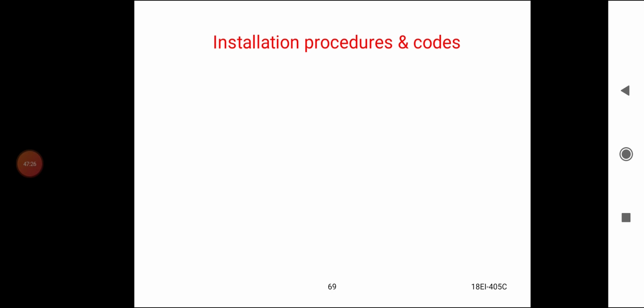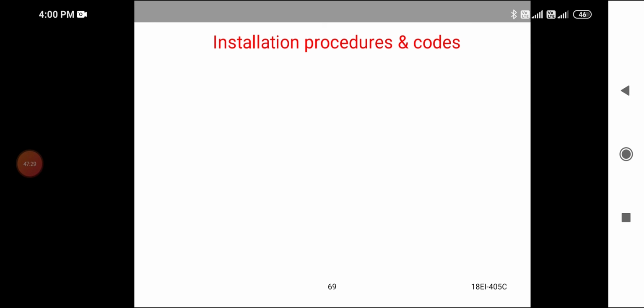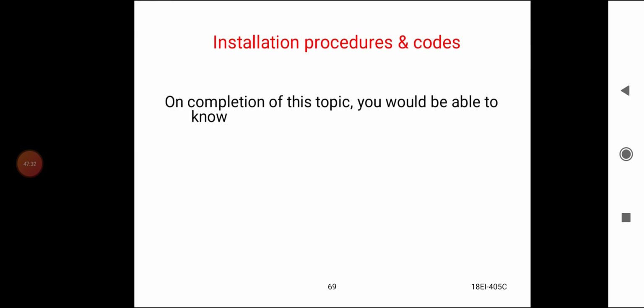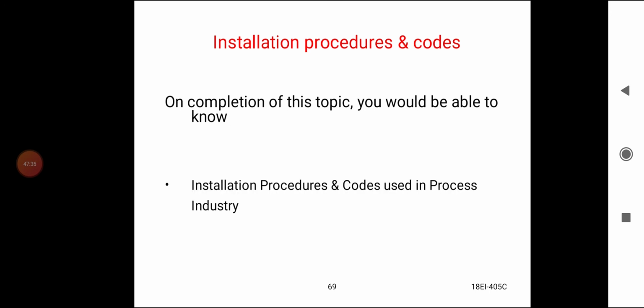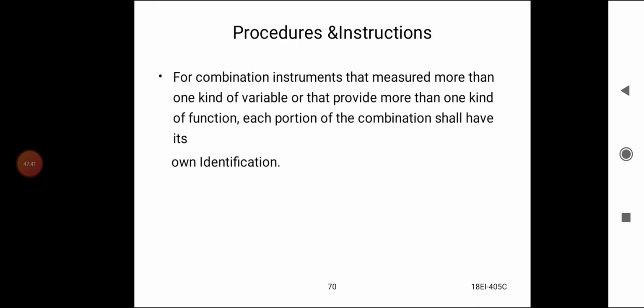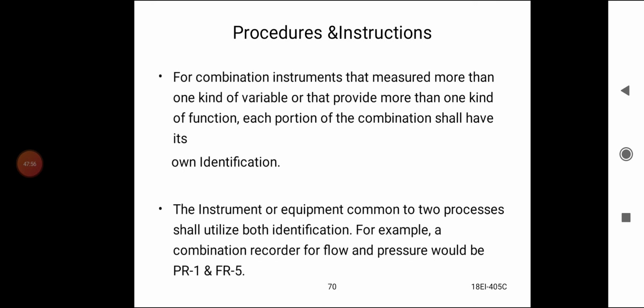Next topic is installation procedures and codes. On completion of the topic, you will be able to know installation procedures and codes used in the process industry. Procedures and instructions for combinations of instruments that measure more than one kind of variable or provide more than one kind of function: each portion of the combination shall have its own identification. The instrument or equipment common to both processes shall utilize both identifications. For example, a combination recorder for flow and pressure would be PR1 and FR5.